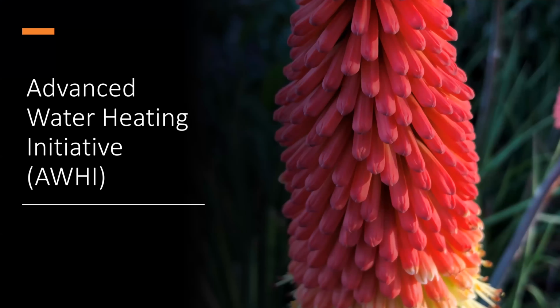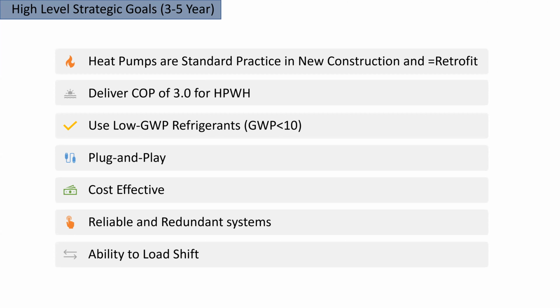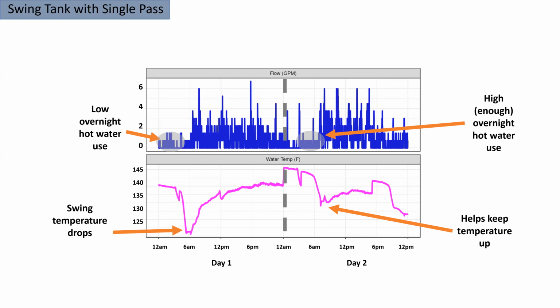This is a really important concept because it allows full COP and full performance on your primary water heating, and you'll get that same COP through the temperature maintenance. This is a key design principle when designing with single-pass equipment.